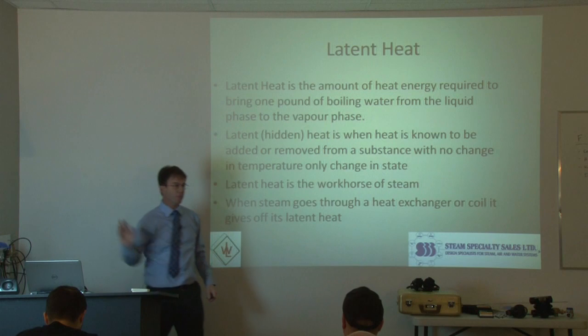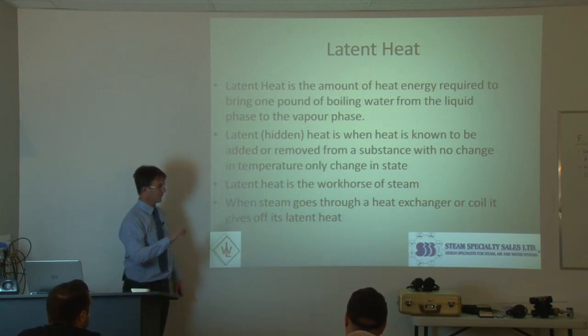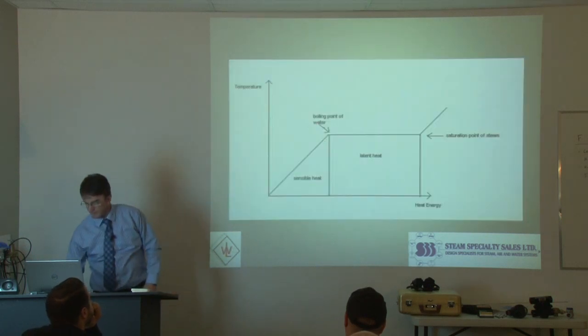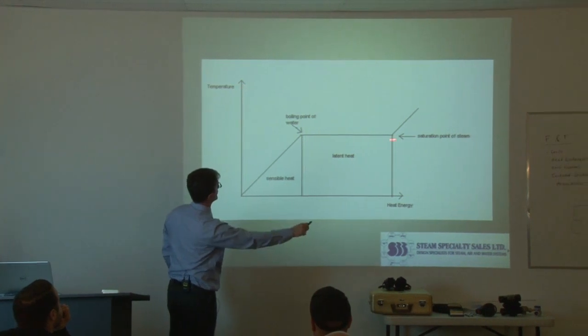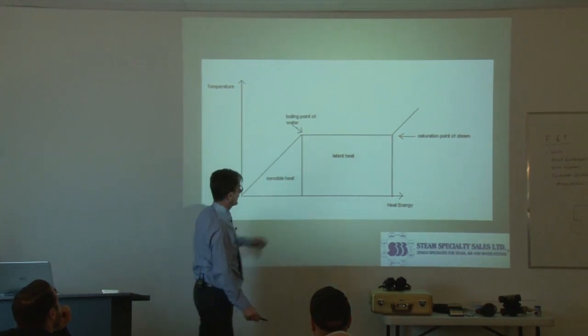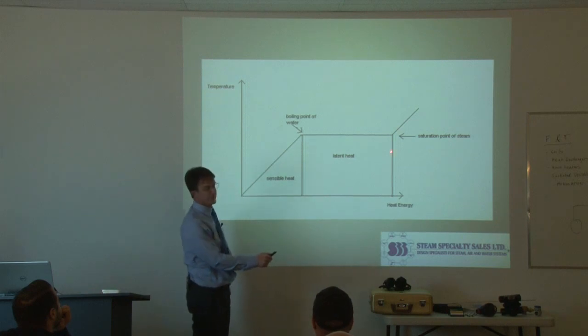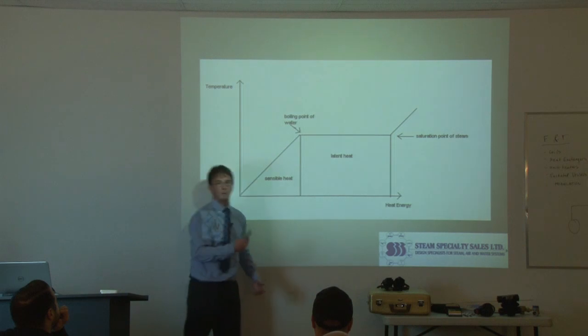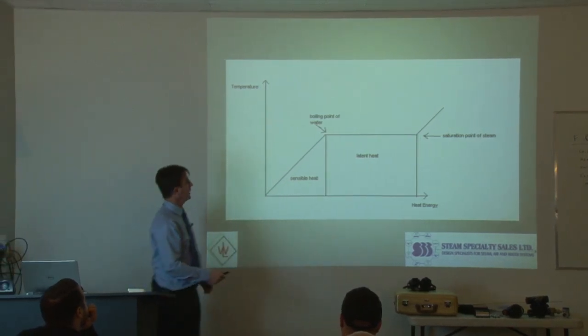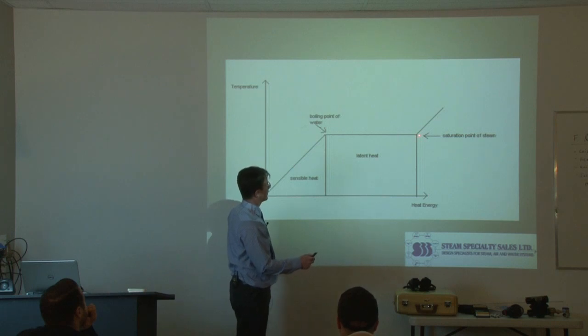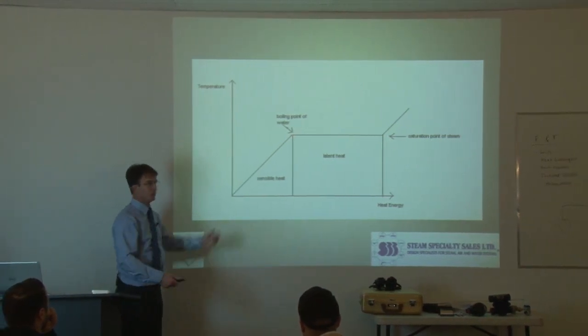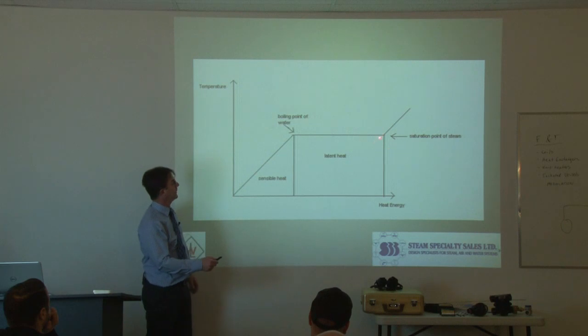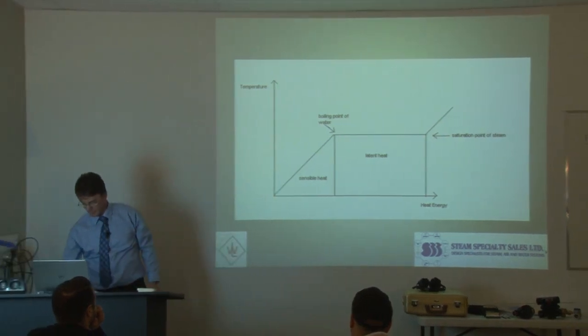Latent heat is the workhorse of steam. So when you're taking steam and you pass it through a heat exchanger or through a coil or through a jacketed vessel, we're giving latent heat from the steam to the process. So your latent heat is this point here — notice the temperature doesn't go up, we're just changing phase. In theory, we're 100% saturated, and this is what a boiler tries to do. Unfortunately, no boiler is 100% efficient. And then when we bring this steam into our process, we give up this heat and turn it back into liquid, which is what we call condensate. So steam condenses and turns back into a hot liquid that we call condensate.